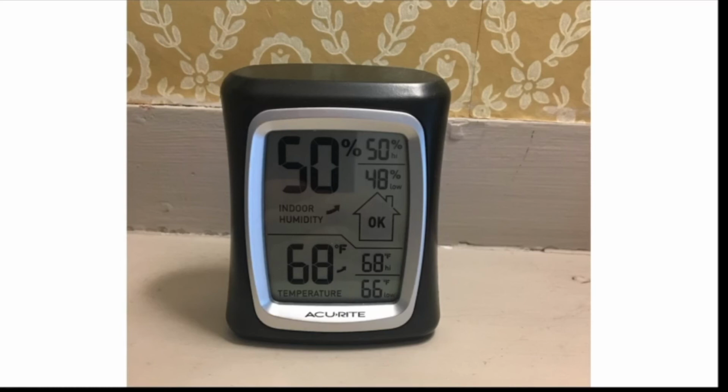We weren't really sure how the humidity was going to behave after we removed the old combustion-based system, so we opted for a low-tech, low-cost monitor before installing a potentially very expensive dehumidification system. And just keep in mind, we could not add humidity in any way. In the winter, the humidity levels actually improved quite a bit once the big makeup air system was removed. The variable speed equipment easily maintained the summer humidity between the desired 50 to 55%, even during the very hot, humid days. So no additional dehumidification was required.